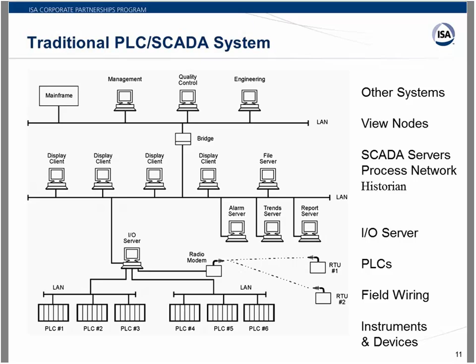So if we look at this from the bottom up, we have our instruments and devices. We move up to our field wiring. We have PLCs, and you'll see on the drawing here, they're called RTUs, or remote terminal units. You'll have a number of servers, the first one being the I/O server, and this is the one that gathers all the information from the PLCs or sends data tags down to the PLCs. You'll have a number of other servers, so you'll usually have an application server, there'll be a historian, and then alarm servers or whatever functionality is required. All of this is connected with a process network. You'll have view nodes, which your operators will work with, and then you'll have a connection up into other systems, a higher network.